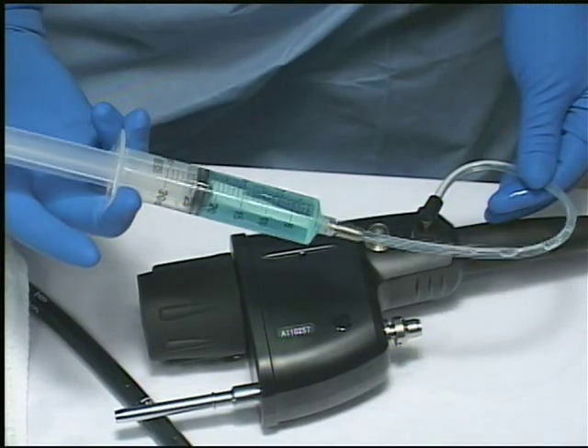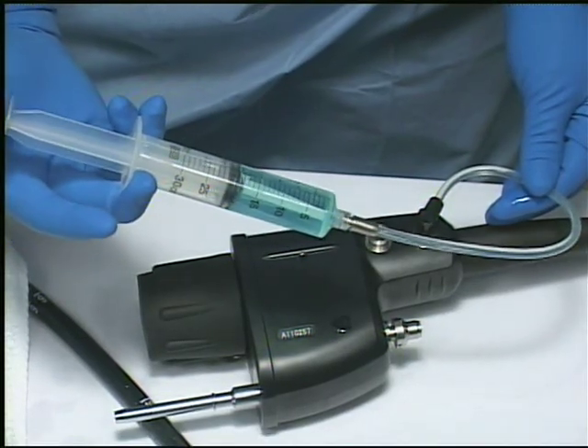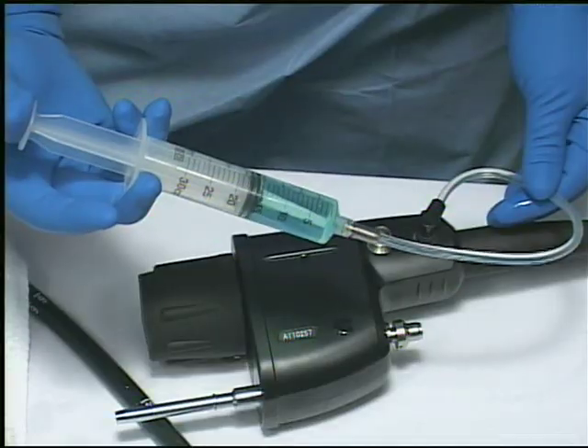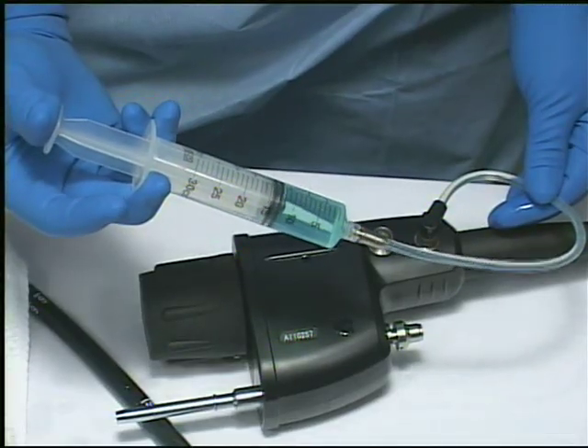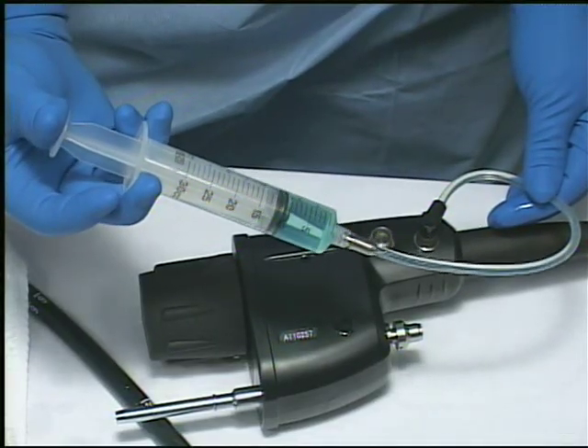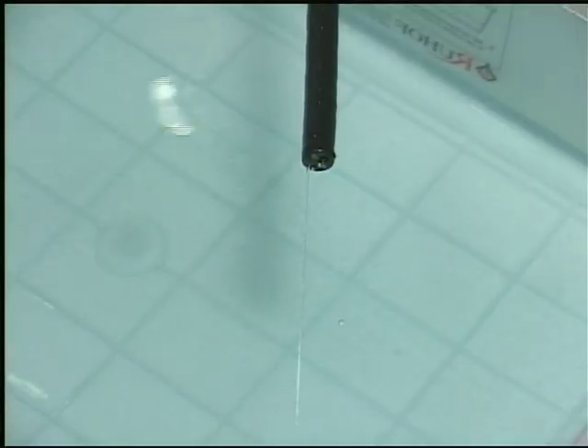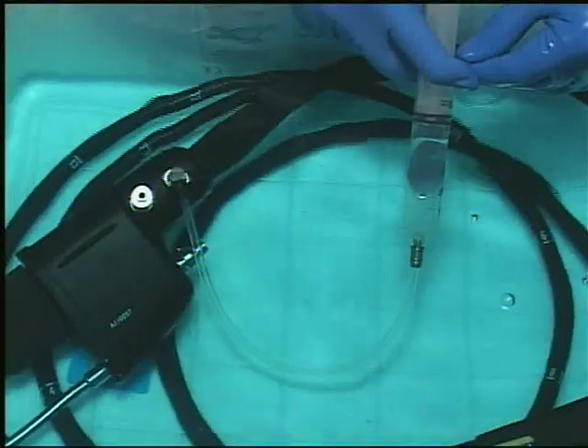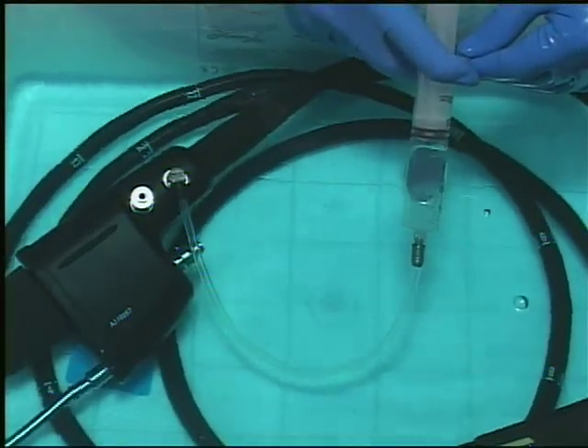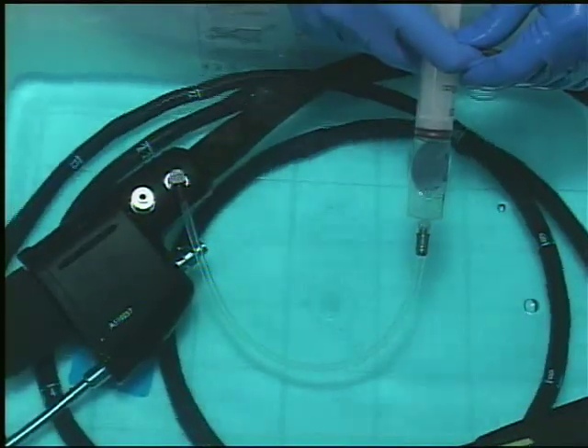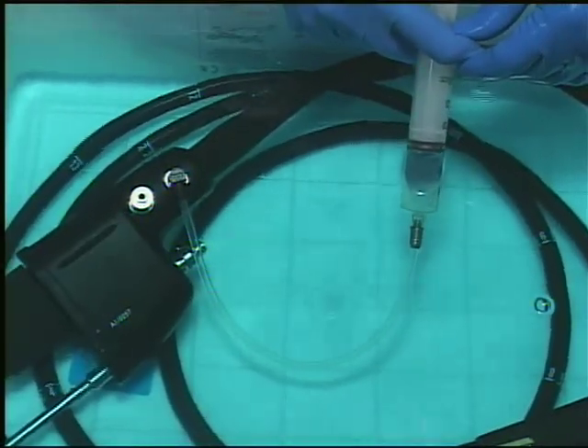Now, inject cleaning solution into the water jet channel just as you would for all other internal channels. Make sure the detergent solution exits the scope's distal tip. Allow the channel to soak in detergent solution for an appropriate time period. After rinsing and drying of the water jet channel, fill it completely with a high-level disinfectant.